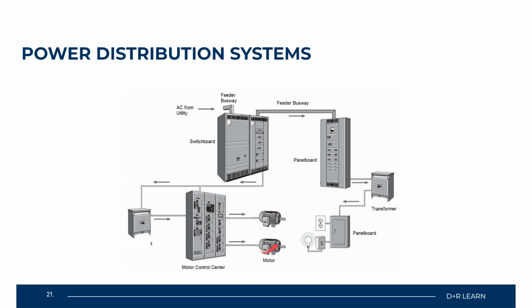So if we needed to power these motors over here down at the bottom, our power is going to come through and be stepped down to whatever the voltage is for these motor systems. So if this is a three-phase 240 system here, we will have the power reduced from 600 to 240, and then we'll be able to power these motor systems down here. Now, you also have your MCC, your motor control center. Let's remember this here. Your motor control center is what's going to be used to isolate power or send power to your motor systems. This is where you're going to be able to see the lights: either green, red, or yellow. If you have an issue and the motor is not running, it'll send a signal back that will turn the light red for off, but then you'll also have your yellow light on for, hey, we've got trouble, an alarm, something's wrong, we can't move any water with this motor system.